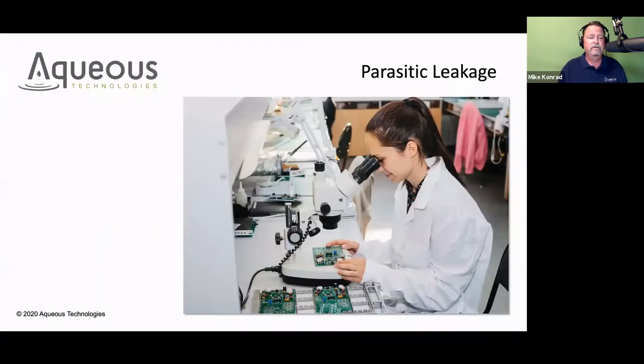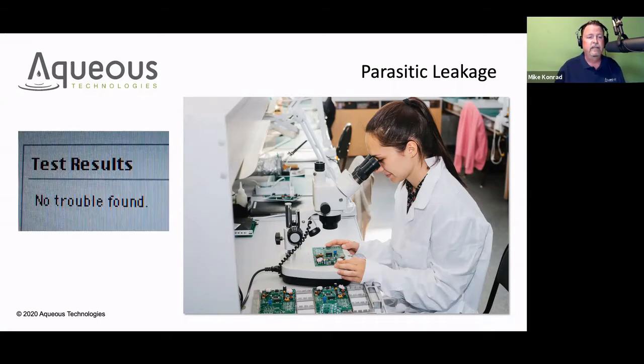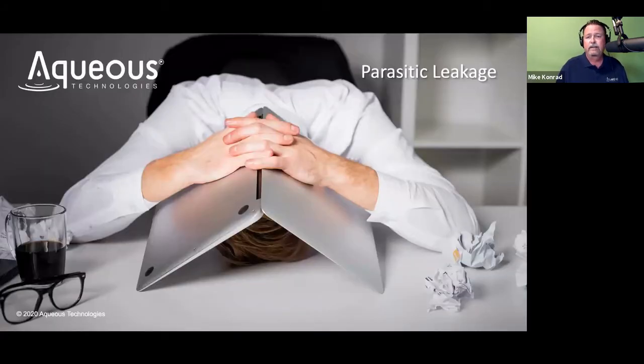The manufacturer is located in a climate-controlled, humidity-controlled, very stable climatic environment building, and they run a test on it. They have their test engineer run it, and they get the dreaded no trouble found, right? What's the acronym for no trouble found? NTF? I suggest there's two acronyms that are appropriate in that situation, NTF and WTF. And that occurs when they can't duplicate the problem. The customer swears there's a problem, the manufacturer tests it in their lab, and there's no trouble to be found. It's a very frustrating situation.